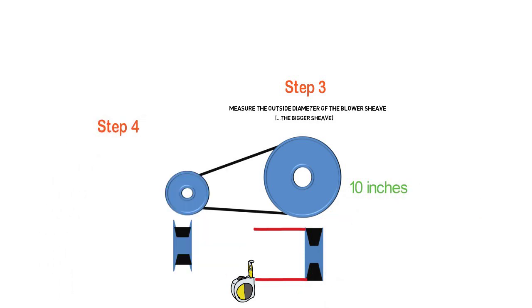Next, we're going to measure the motor's sheave. Now, this one, you have to be a little bit more careful. You have to measure where the belt is riding, not the outside diameter of the sheave itself. Look at the red line. See how they're stopping where the back of the belt is? That's the point you want to measure. In this case, we have three and a half inches. Pretty simple so far.